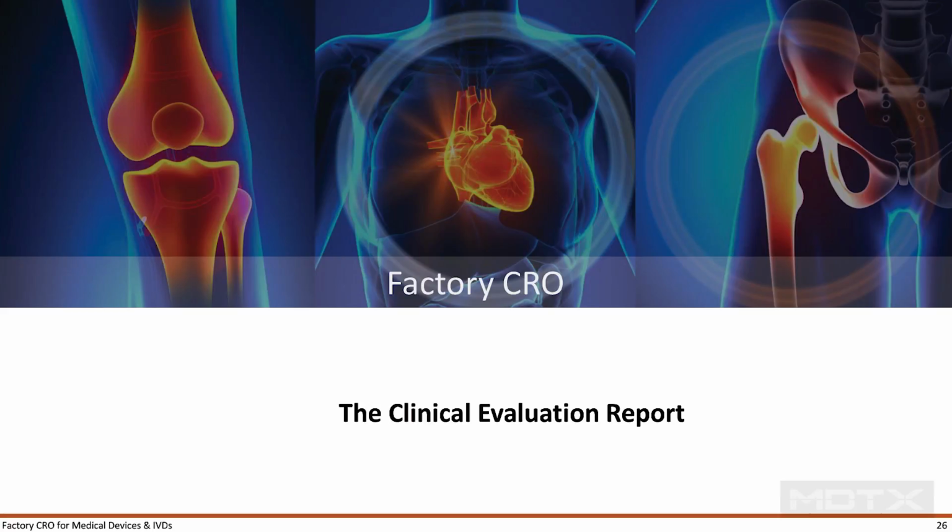So for human data, is ISO 14155 required? Let's say you're accumulating human data in the United States and you have really good clinical practices. Is that the whole thing, 14155? I think it is. The MEDDEV does not state it has to be performed according to ISO 14155. It does say you have to evaluate whether it's acceptable data and why you think it's a good study or why it's not, what the gaps are. And then they say, for example, if it's conducted according to 14155, it should be acceptable. But they don't say that they don't accept other data.